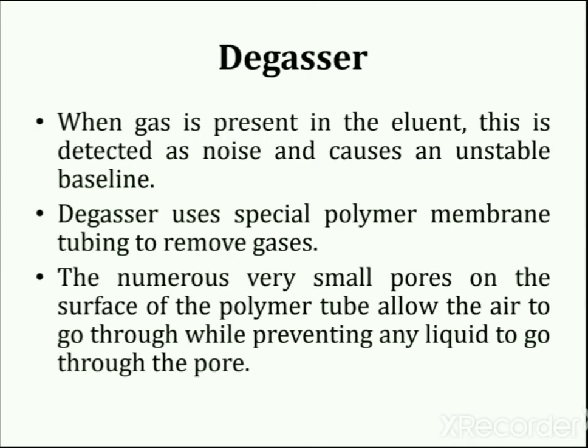The next important part of the HPLC system is the degasser unit. The eluent used for liquid chromatographic analysis may contain dissolved gases such as oxygen that are not visible to the eye. When gas is present in the eluent, it is detected as noise and causes an unstable baseline. The degasser uses special polymer membrane tubing to remove gases — the numerous very small pores on the surface of the polymer tube allow air to pass through while preventing any liquid from passing through.